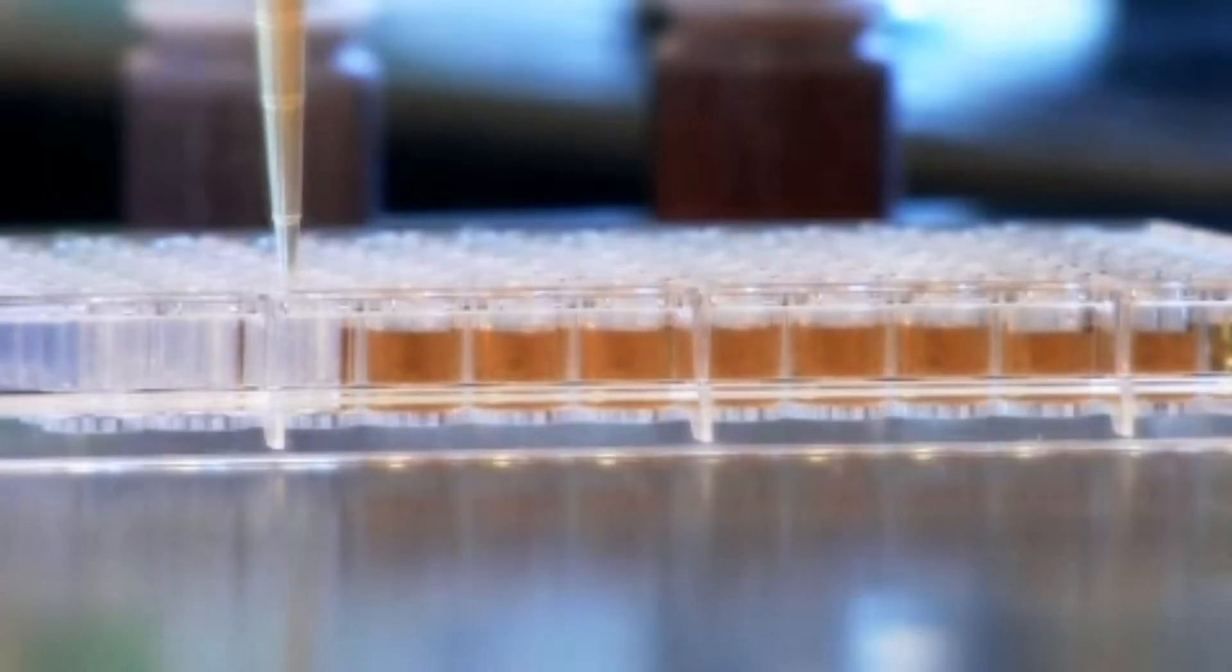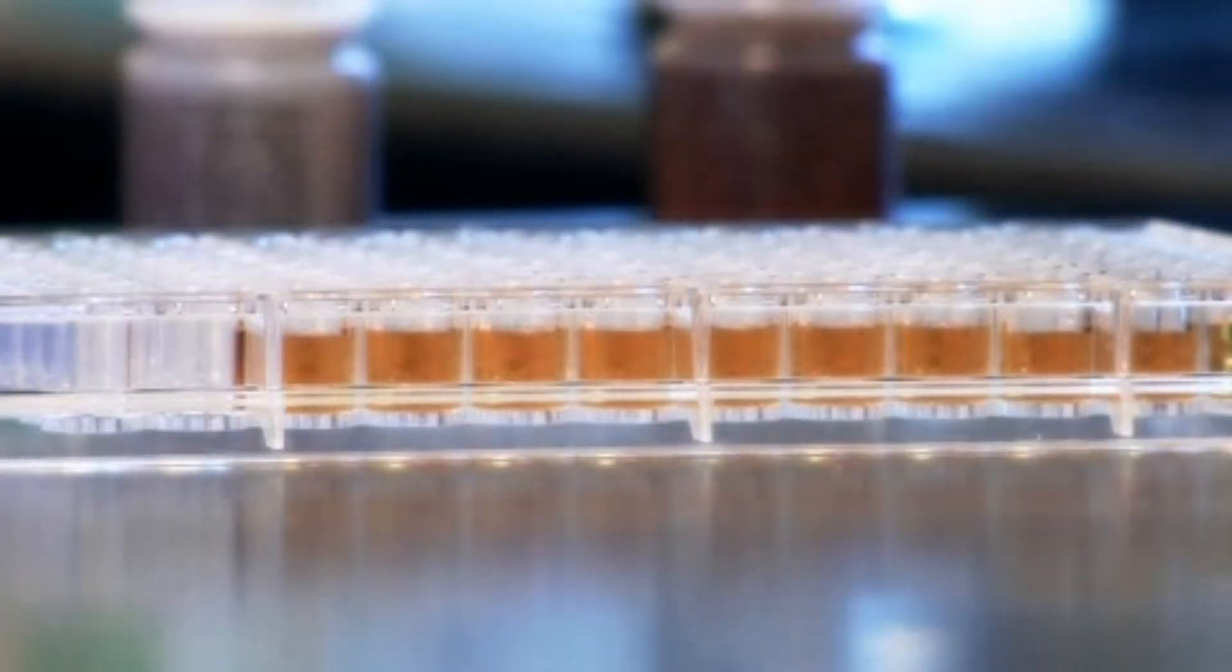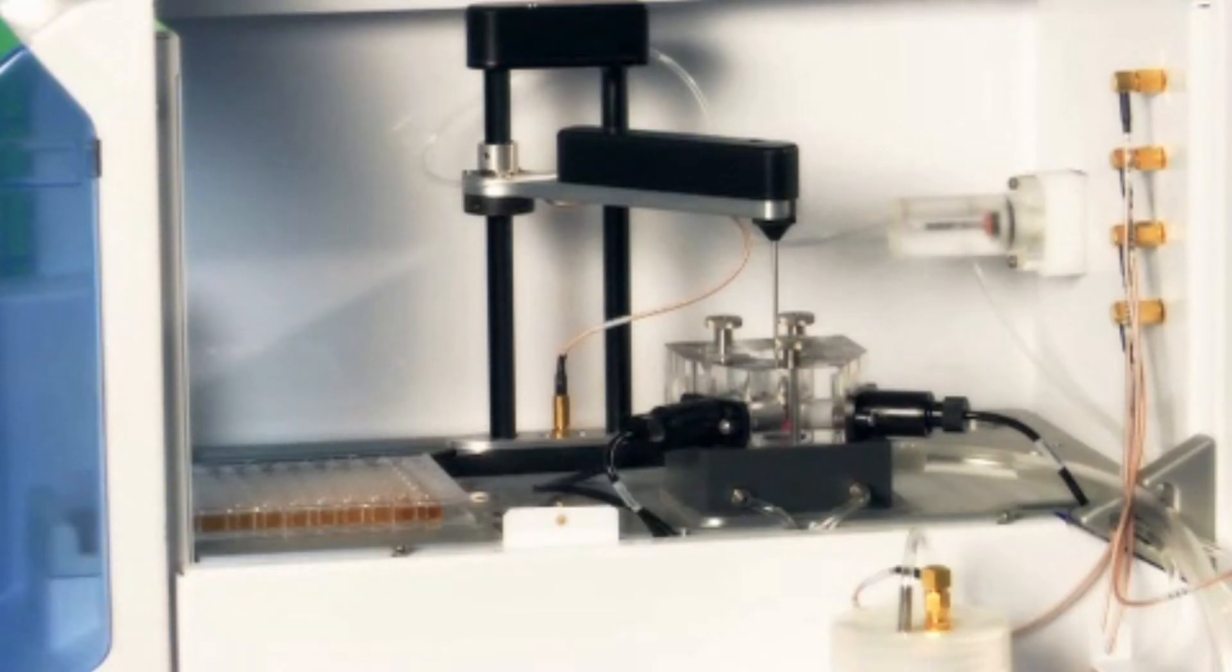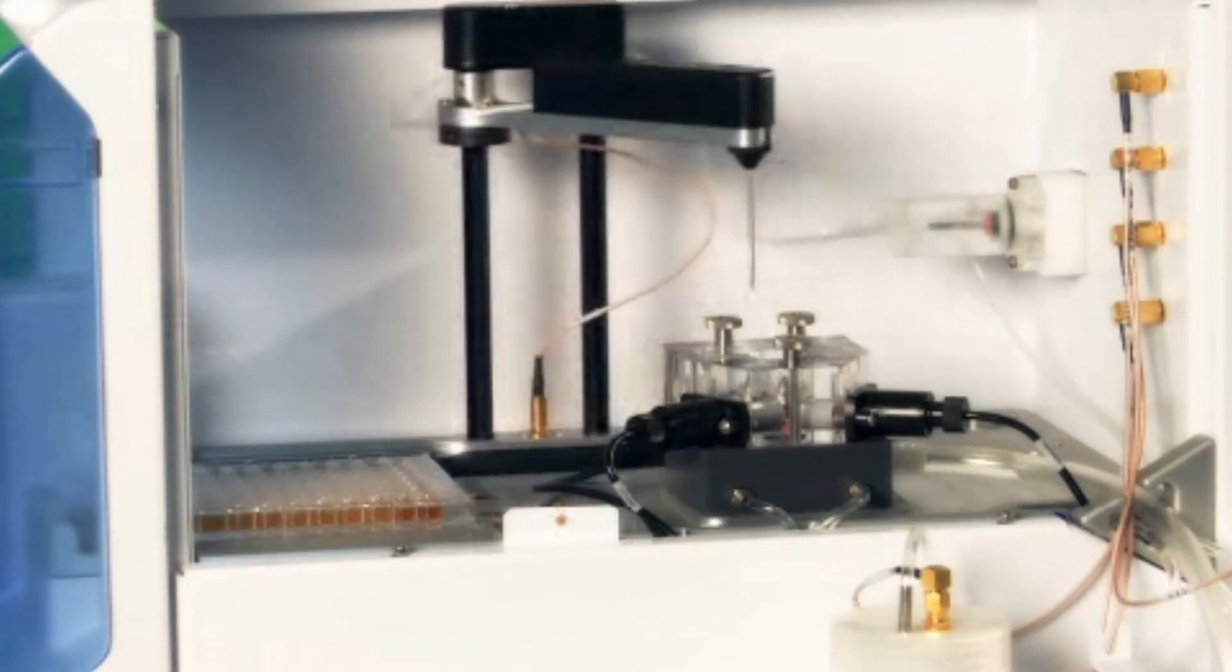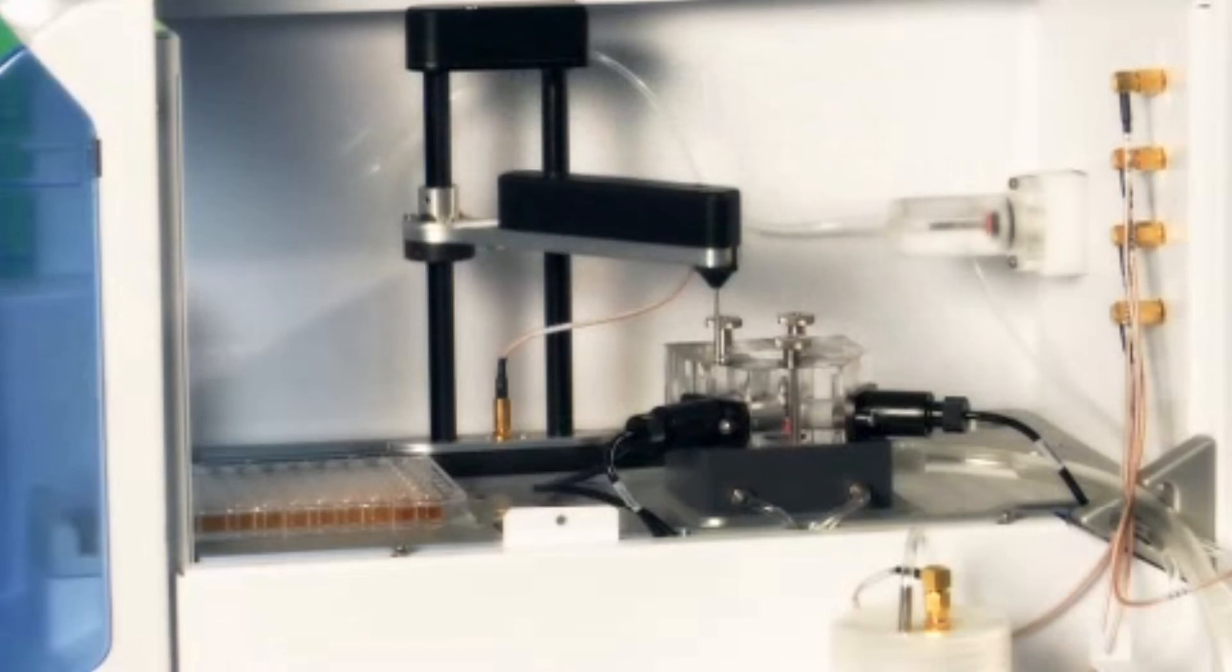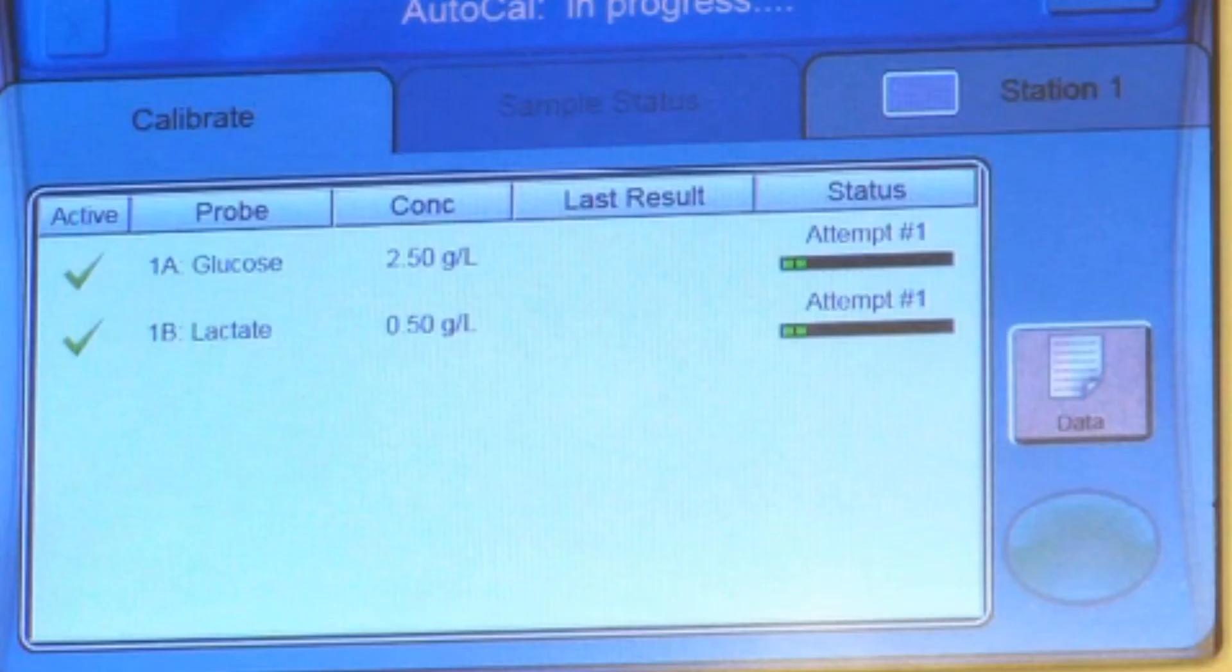Multiple samples can be batched up to 96, and any installed chemistry can be run on any sample in the sequence. Rush samples can be inserted into the queue at any time. Accurate results are available in less than a minute.